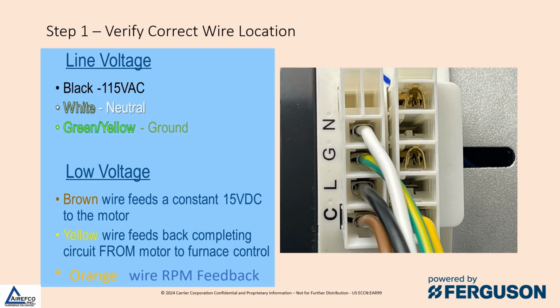You will need to first verify the correct wire location for the line voltage. Normally black is 115 volts. White is neutral and green and yellow is ground. This can vary between the 115 volt and the 208/230. So verify with the motor data that you have for your particular motor.